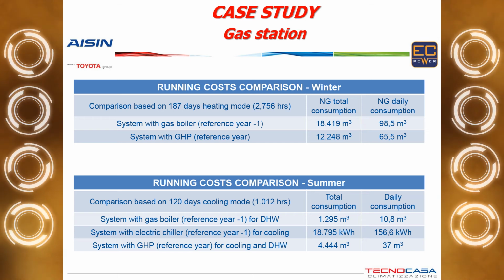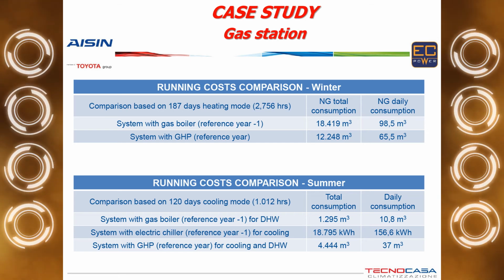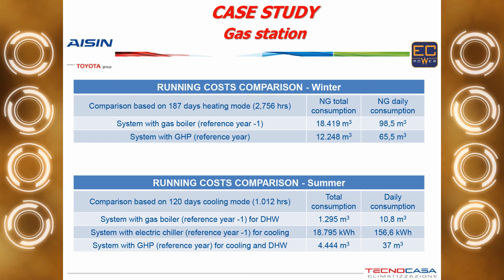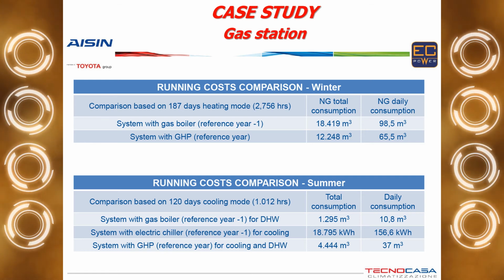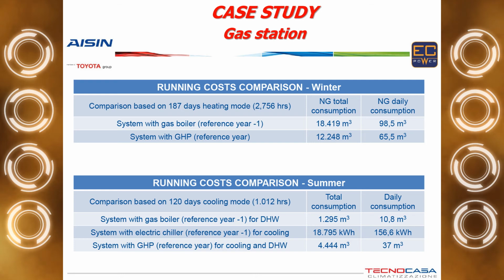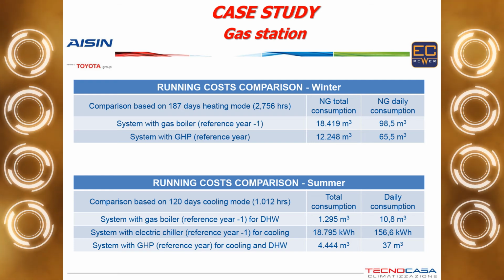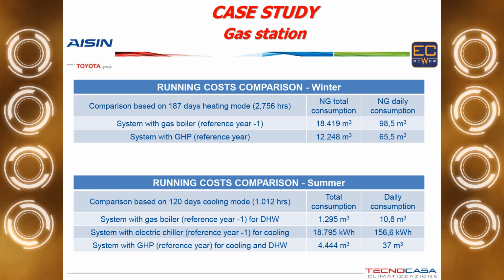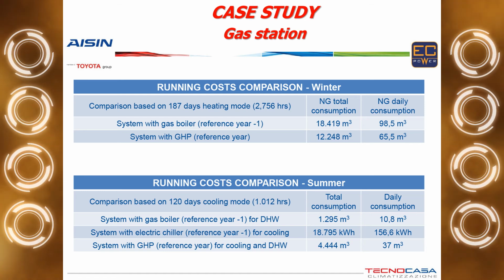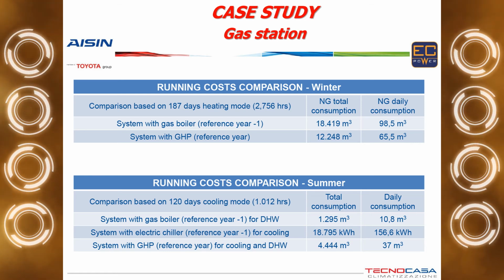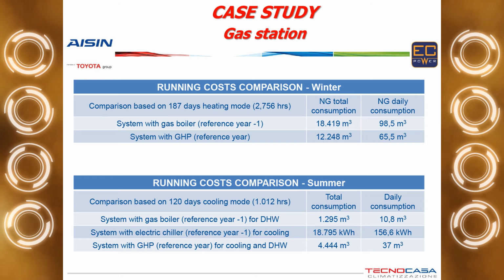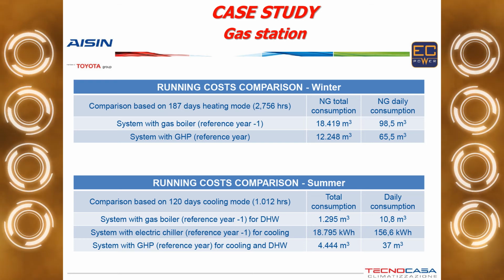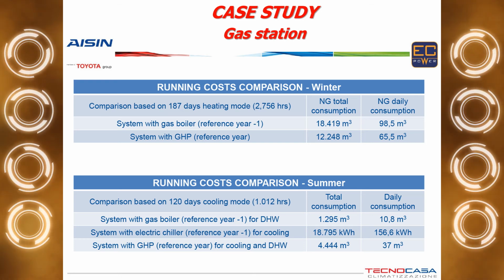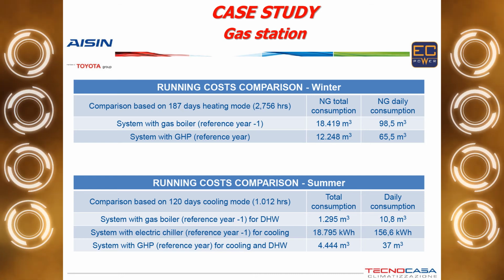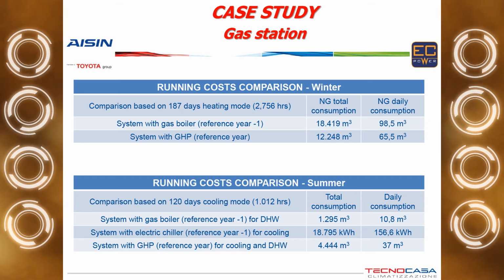156.6 kilowatt hours. But then we also had to calculate how much energy was needed for the production of domestic hot water. So the gas boiler went on with 1,295 cubic meters, which is 10 cubic meters per day only for the showers. All in all, the GHP produced in the 120 days the same amount of domestic hot water by cooling the restaurant and the gas station and using only 4,444 cubic meters of gas, which is about 37 cubic meters per day.